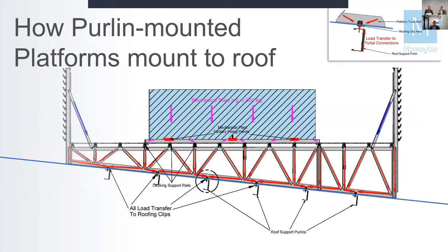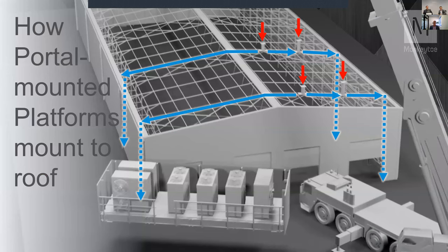The platform has to be fixed to the roof in one of two ways. One's a purlin-mounted option — this shows how those loads are transferred back through to the purlins, whether it's wind loads from the screens or the actual plant equipment on the platform transferring all the way back through to the purlins. The other is the portal-mounted option, where the load goes back through the main building structure — the portals.